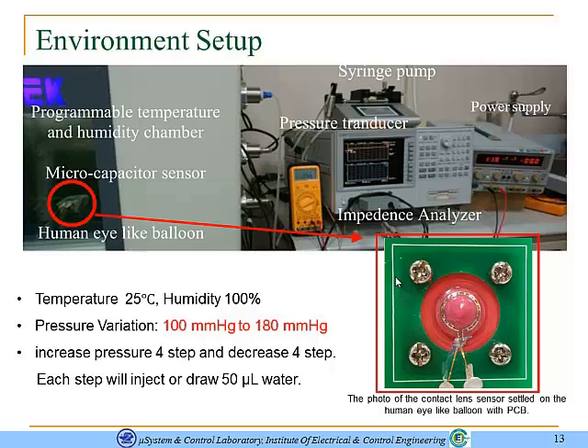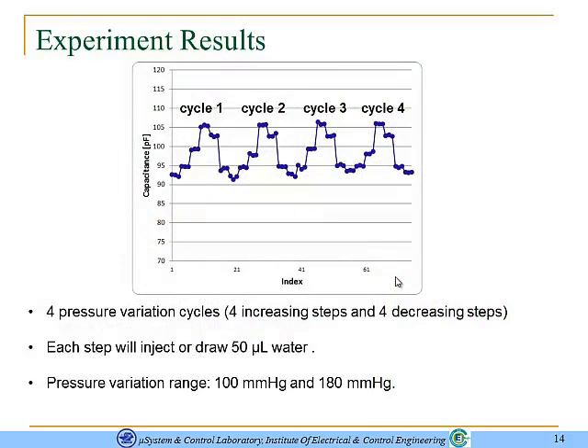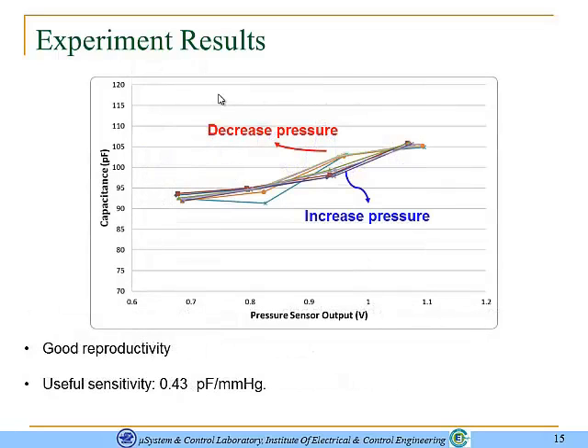Then the sensor was connected to an impedance analyzer, and the capacitance value was measured. And this is my experiment result. Next step, we inject water into the human-eye-like balloon. The next step, we draw the water from the human-eye-like balloon. Each step will inject or draw 50 microliters of water. This figure shows the sensor has good reproducibility and repeatability. This figure shows that our sensor has good linearity and a sensitivity of about 0.43 picofarad per mmHg.